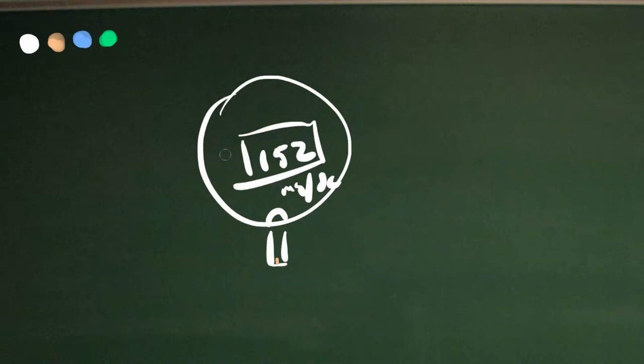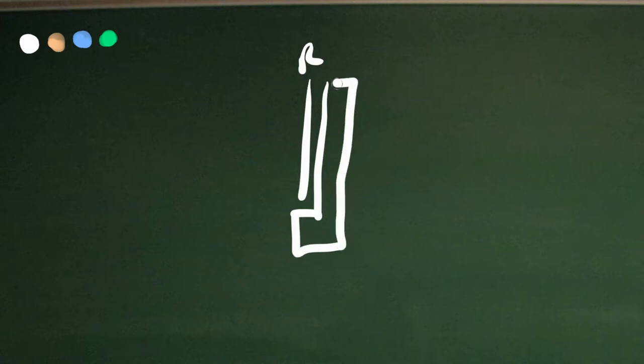So how does this work? It turns out all the action isn't in this device. All the action is actually in the strip. So these strips work on a three electrode system where you have what's called a reference electrode, a working electrode, and a counter electrode.